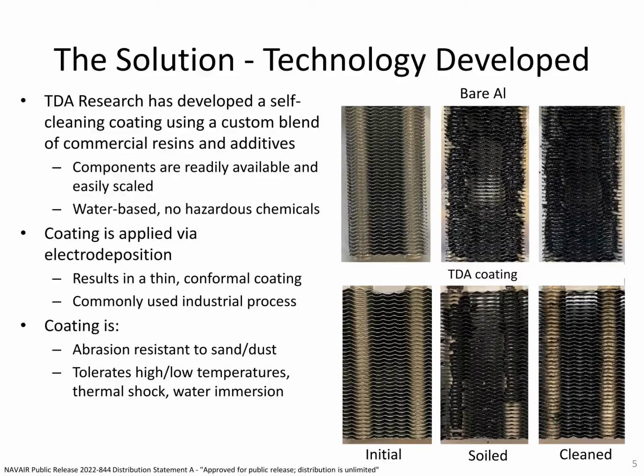We apply our coating via electrodeposition. This technique is a commonly used industrial process, particularly in the auto industry. The part to be coated is immersed into a coating bath and voltage is applied. This causes charged resin molecules in the bath to be driven towards the surface of the part, resulting in a thin, conformal coating. It is this technique that allows us to coat the complicated internal fin geometries of the heat exchangers, which is not something that could be achieved by a spray or dip application.